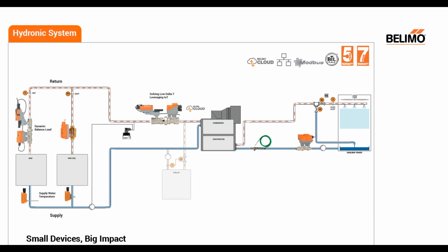The key to achieving perfect hydronic control is maintaining design flow at the terminal units, differential pressure across the control valves, or simply system balance under different conditions. Small devices that have a big impact on the overall hydronic system.